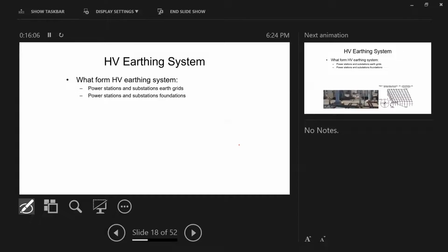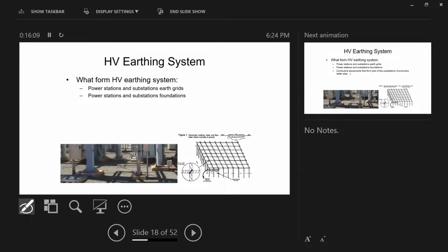Now, all this information, guys: everything conductive makes up our earthing system, including wet timber poles. You have to be very careful. Wet timber poles are conductive because they are wet. During rain, you have water embedded inside them, and it will drive down their resistance. Inside the substation, every single piece of steel is considered part of your earthing system. If it's bonded, better. Why? Because you put it at the same potential level. If it's not bonded, it will cause a major issue.